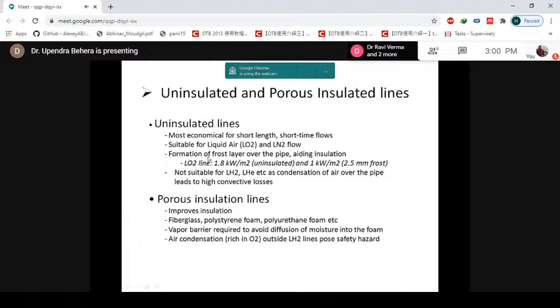And there is the formation of frost. Once you transfer in a bare tube or bare transfer line, the atmospheric moisture and carbon dioxide settle, whereas the cryogen gets evaporated, and this carbon dioxide and moisture make a frost over the line, and because of that the heat transfer is minimized.